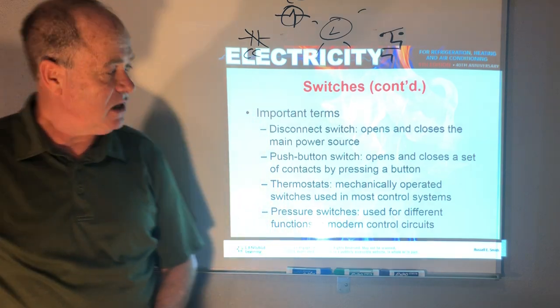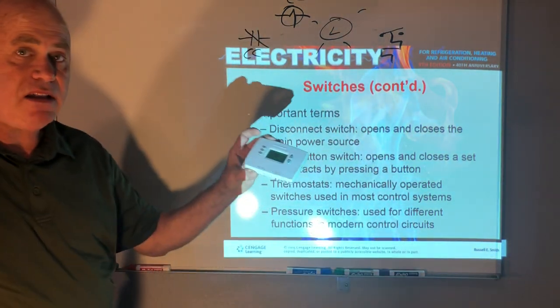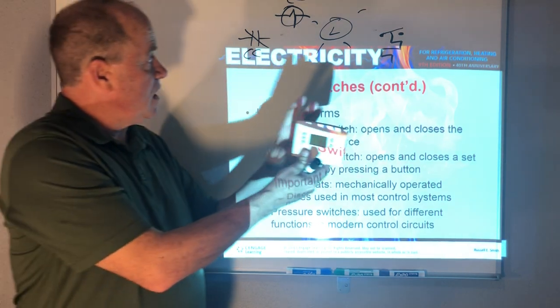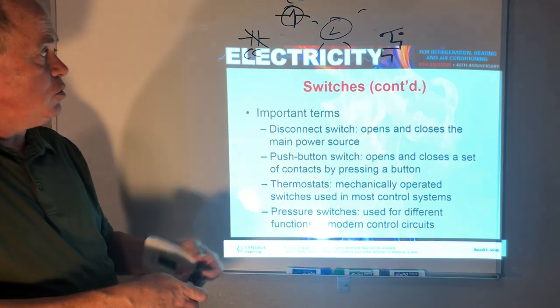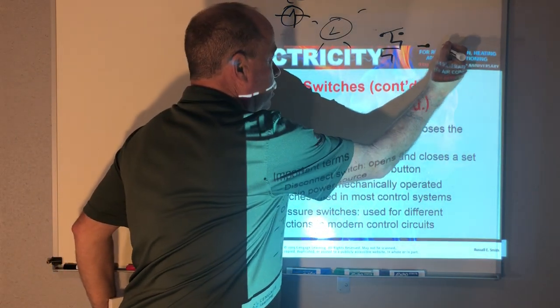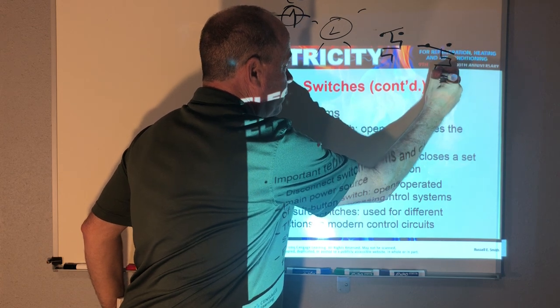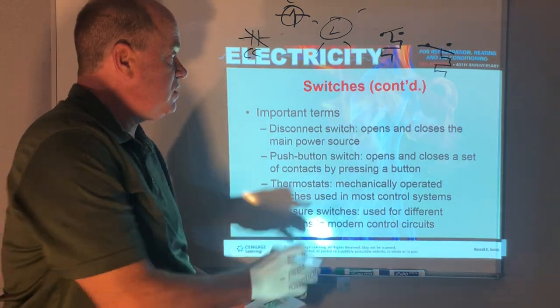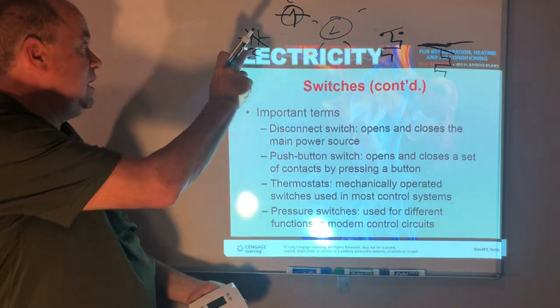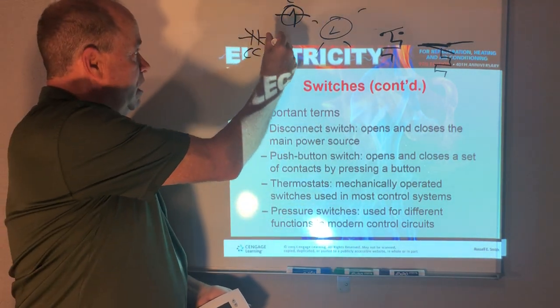Now thermostats, as I just drew, inside this air conditioning thermostat, we have a heating thermostat and a cooling thermostat, which would be drawn below the line. So that if the bi-metal gets warmer, this rises up and closes and then brings on the cooling, which normally would like energize a contactor coil. And then this would close and then bring on a compressor.